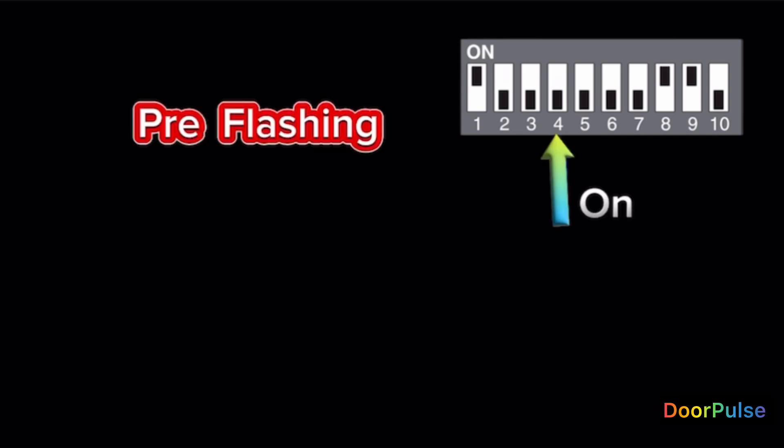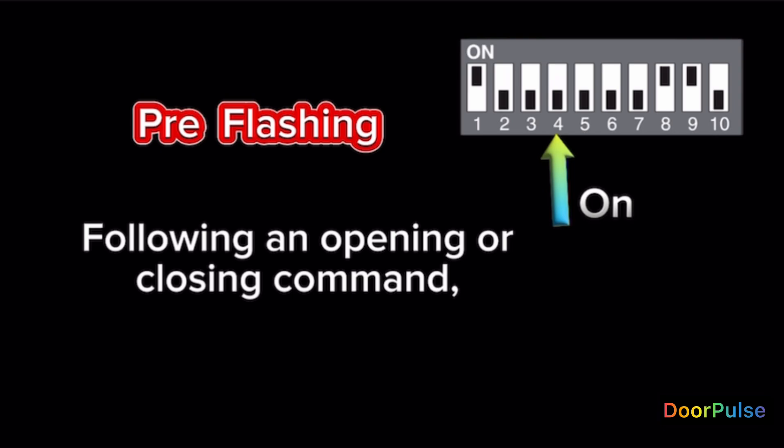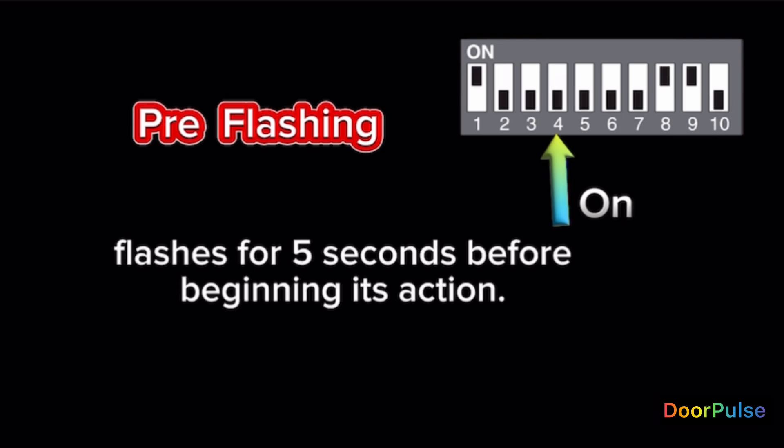Switch 4 ON. Pre-flashing. Pre-flashing while opening and closing the boom. Following an opening or closing command, the flasher and/or luminous crown connected flashes for 5 seconds before beginning its action.